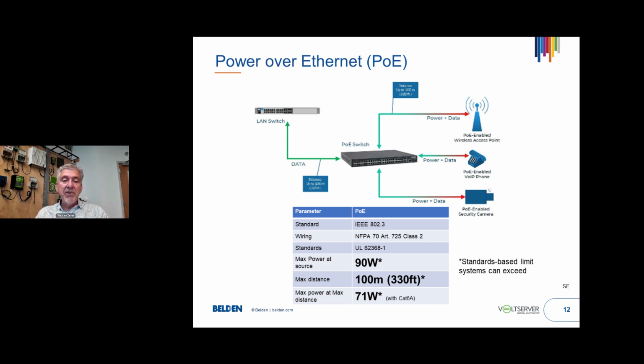As many of you know, there are distance and power limitations with PoE. With the latest standard, 802.3, we're currently at about 90 watts at the source, and as usual the max distance is 330 feet or 100 meters. It's quite lossy at high power over long distances, and that's another reason it complements fault managed power so well—by reducing the line lengths of the PoE nodes, you get higher efficiency and better data quality.